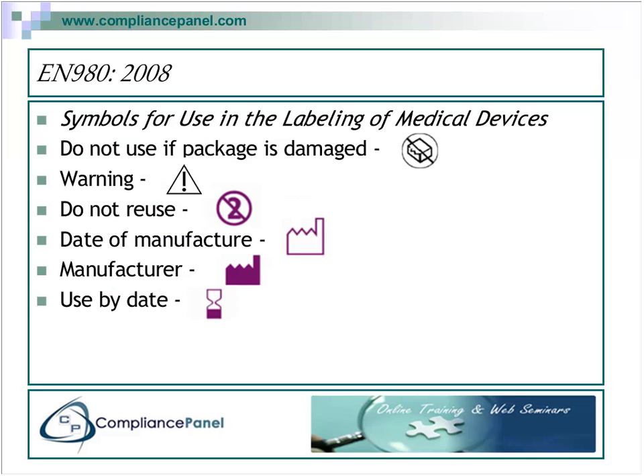Do want to cover this for a second. There is a European standard that is titled Symbols for Use in the Labeling of Medical Devices, and I've included a few here. Do not use if package is damaged is that particular picture. Warning, do not reuse, a 2 with a line through it. Date of manufacture and manufacturer, a little different, so you don't need to write manufactured by LifeTech or company. You would just put this icon and you just write LifeTech after it. Use by date is that almost half-filled hourglass. Instead of expiration date, you just put that and the date after that.